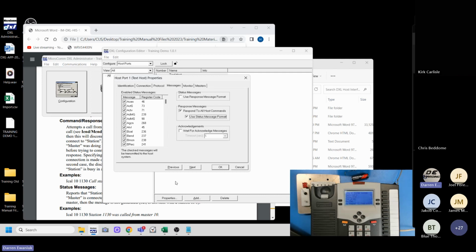So if it missed the call request and the intercom system sent a call request message out and you didn't act on it, now the intercom system knows that the call request button is pressed, it's in the queue. Someone presses the button again, it will not resend that intercom call request because it's already in the system. So that may mean if your system, for some reason, didn't process a message, then the intercom system thinks it's calling in, your system doesn't think it's calling in, and the intercom system will not retransmit that because it's already in the system.